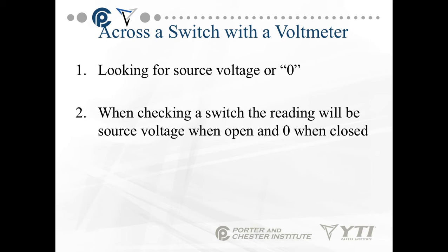When you check across a switch with a voltmeter, we're looking for source voltage or zero. The reading will be source voltage when the switch is open and zero when it's closed. Voltage readings across an open switch is source. Voltage readings across a closed switch is zero.